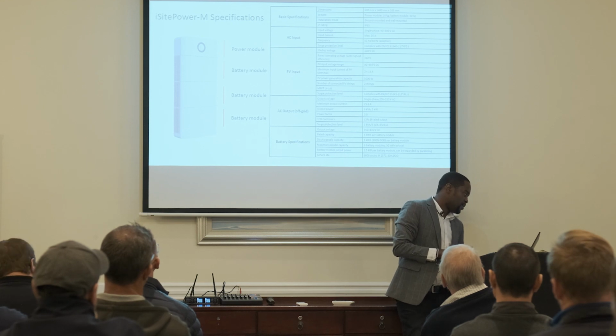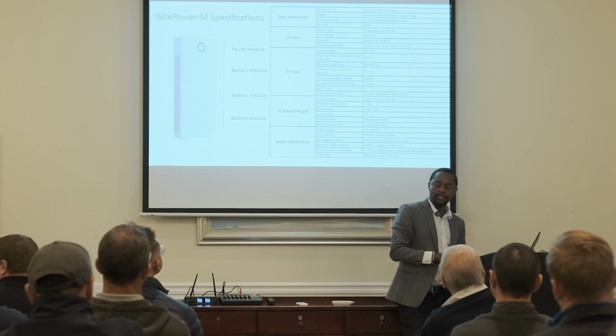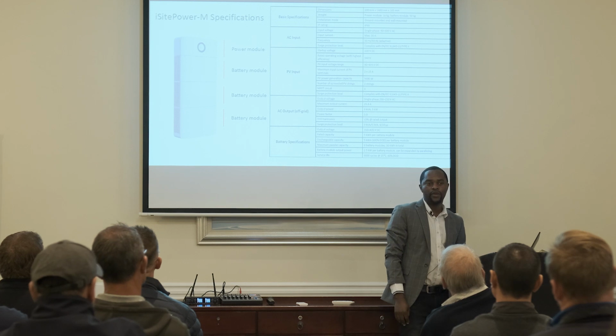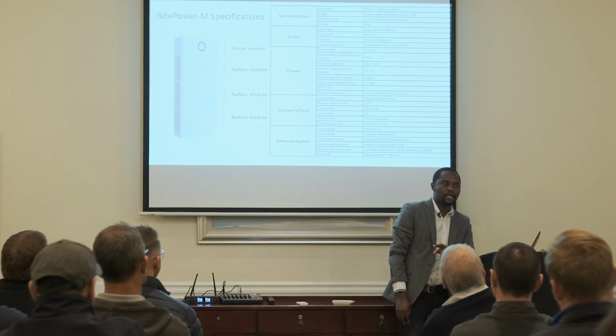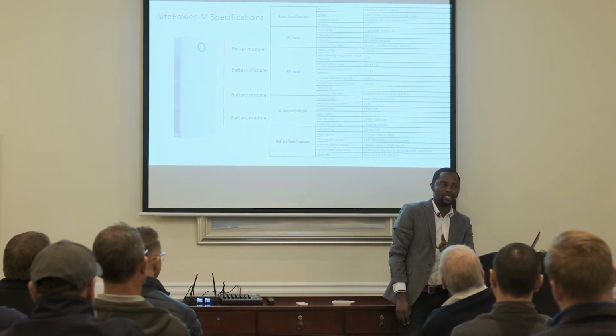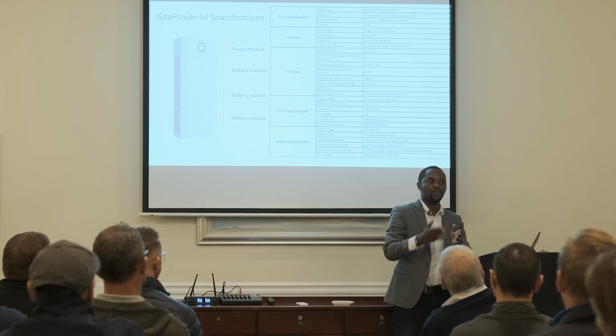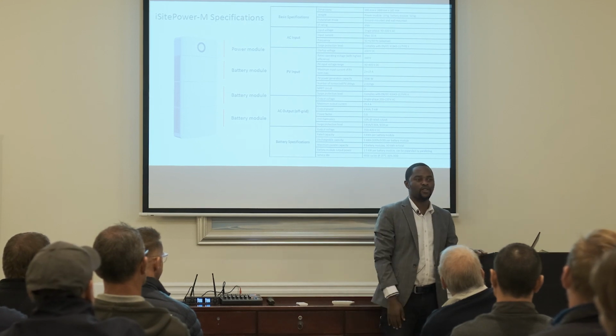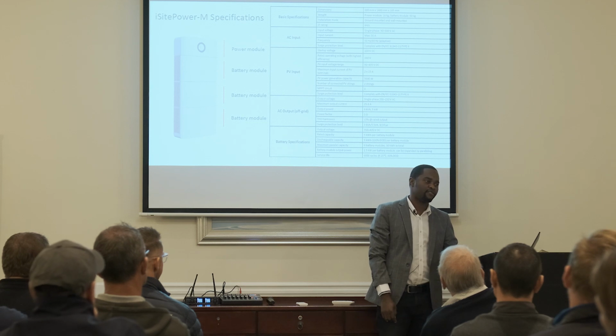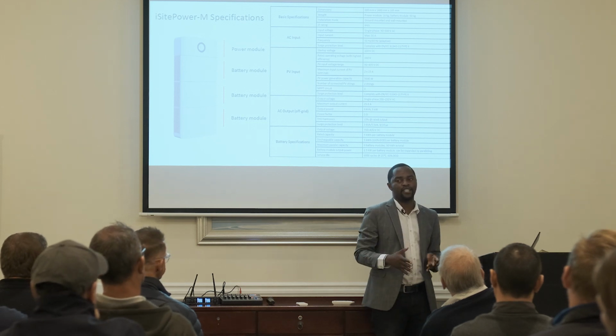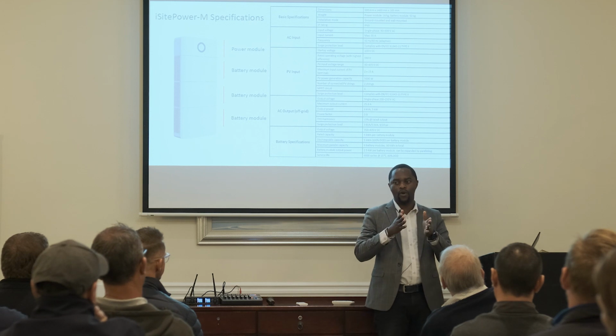Looking closely now with the basic specifications, it's 6 kg, the power module. Then you can parallel these, by the way, up to 3 on a single phase configuration. So you can't put one per phase and get a combined 3-phase output. I think that's also important to clarify that. You can only put them on one phase. So you are building your power only on one phase.